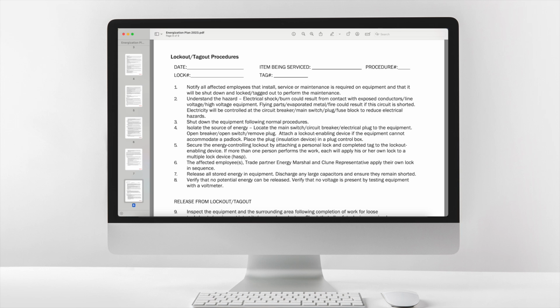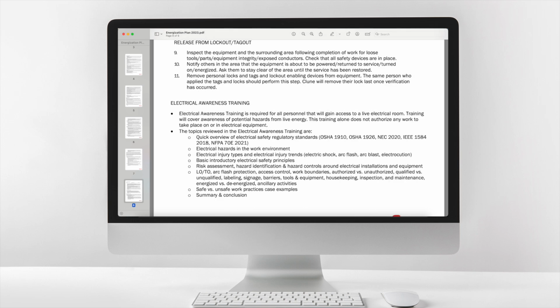Release from lockout, tagout. 9. Inspect the equipment in the surrounding area following completion of work for loose tools, parts, equipment integrity, exposed conductors. Check that all safety devices are in place. 10. Notify others in the area that the equipment is about to be powered, returned to service, turned on, energized. Ask them to stay clear of the area until the service has been restored. 11. Remove personal locks and tags and lockout enabling devices from equipment. The same person who applied the tags and locks should perform this step. Clune will remove their lock last once verification has occurred.